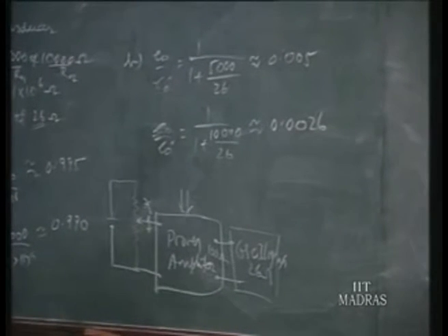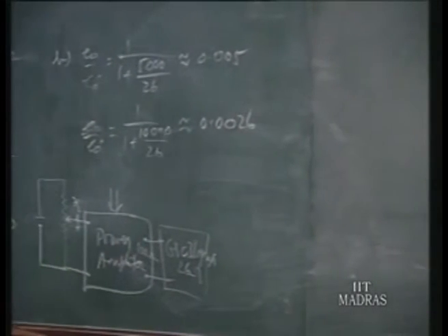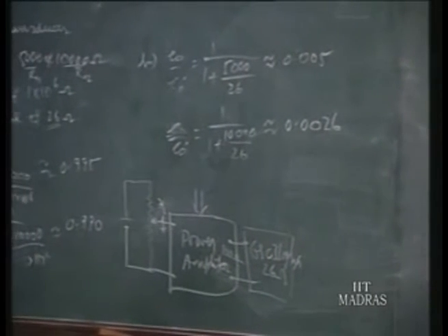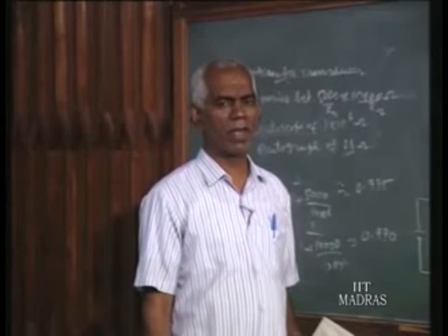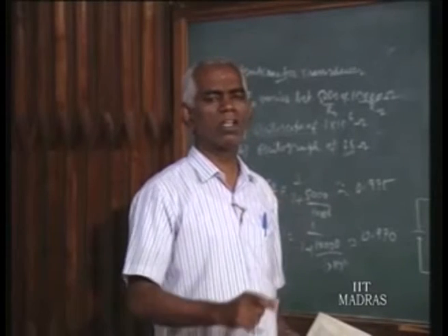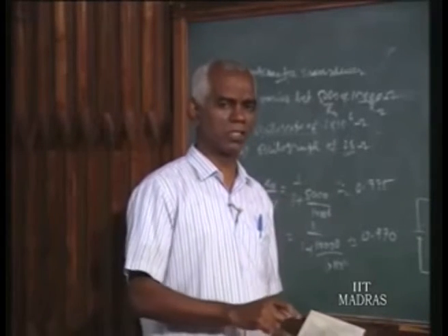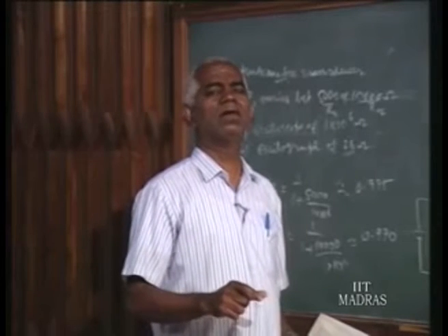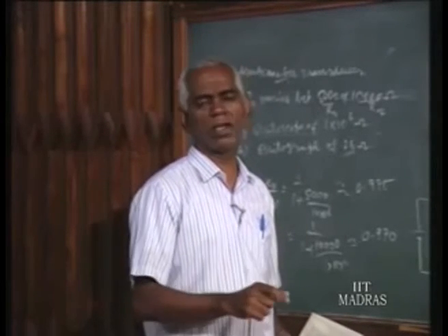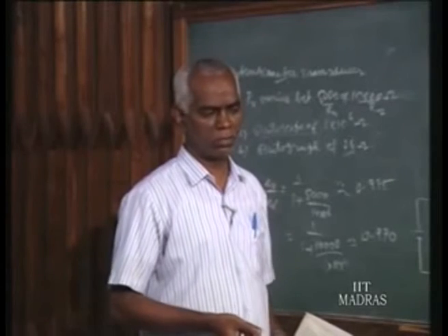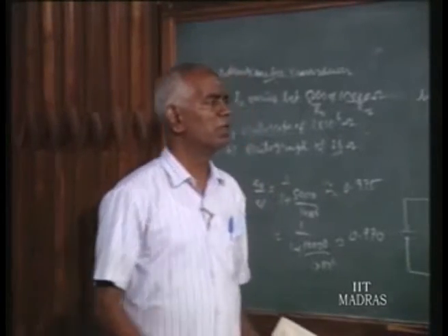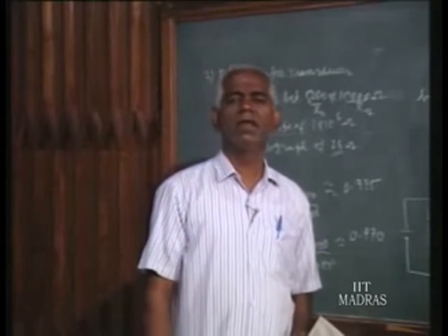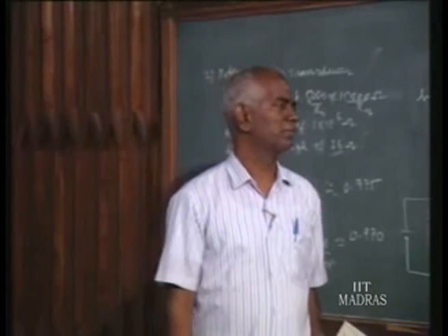Next we are going to see how to make use of the 4-quadrant diagram. We already learned the 4-quadrant diagram, where the different error sources within the instrument are identified by drawing the signal flow diagram, and we find the total effect of the error source on the input signal. From the total error we obtain a suitable least count, and that is what you are going to use when we manufacture the instrument. That is a design problem. How to decide the least count of a proposed instrument.